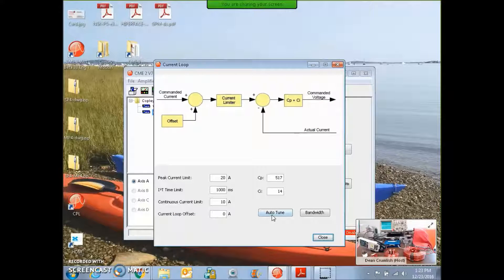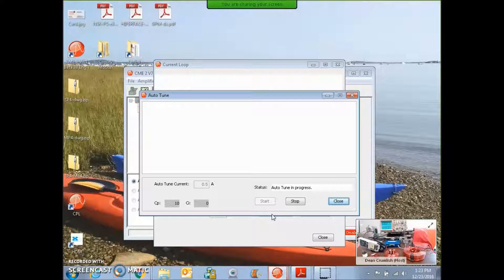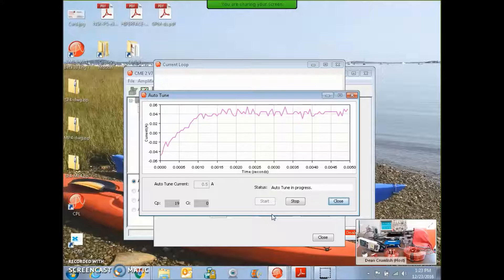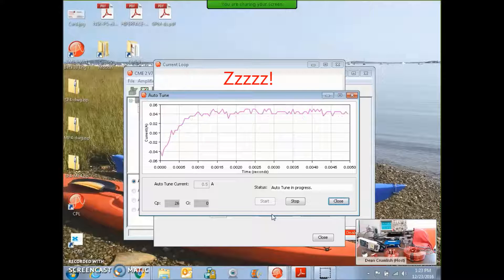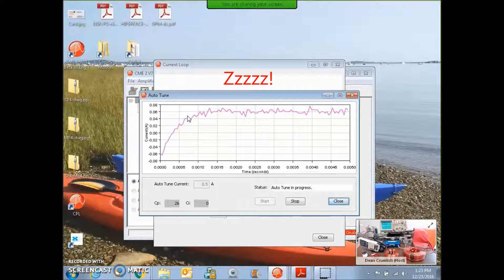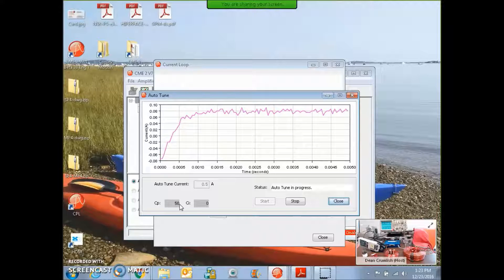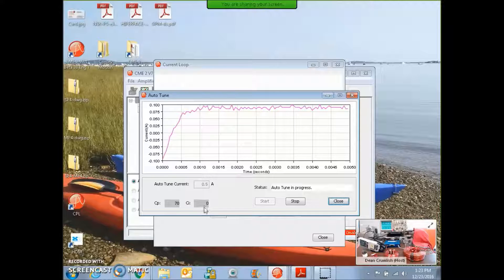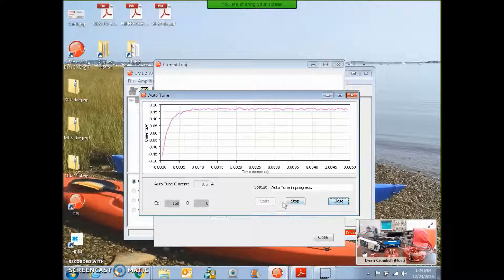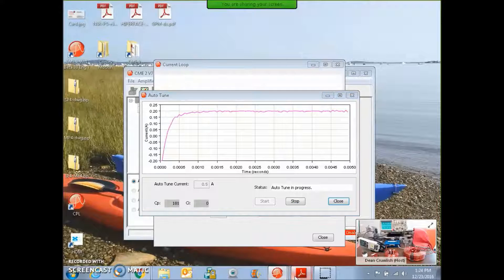We also have an auto tuning and we can use the auto tuning to tune the current loop. It sets the integral to zero and it cranks up the p term until we see some overshoot. Then it backs down a little bit. Then it cranks up the integral term. We'll see what the calculated values are and how that works.